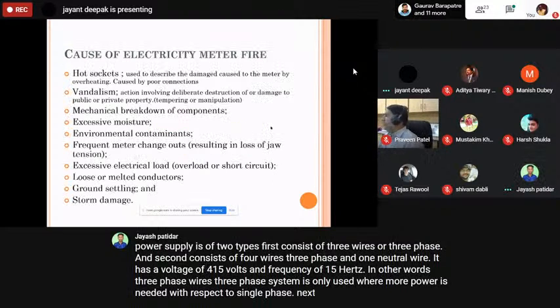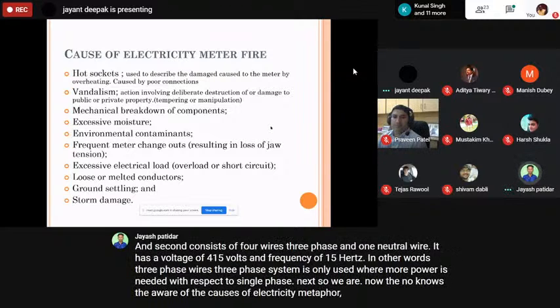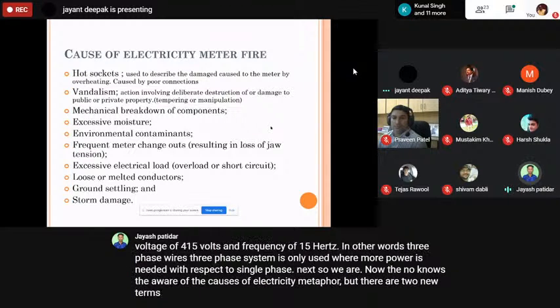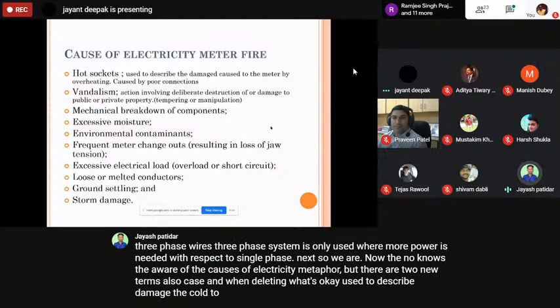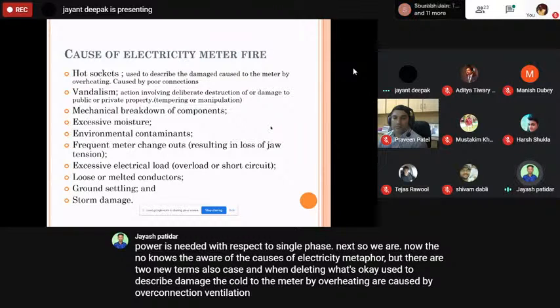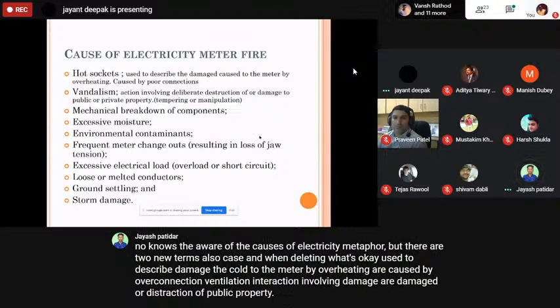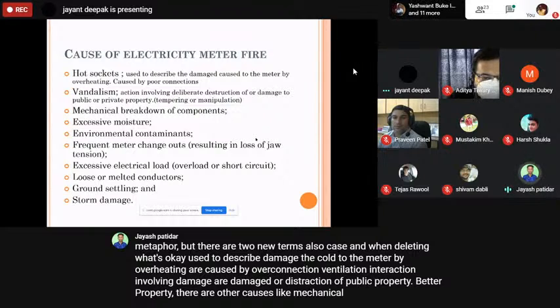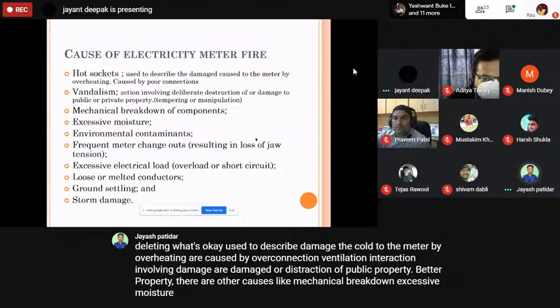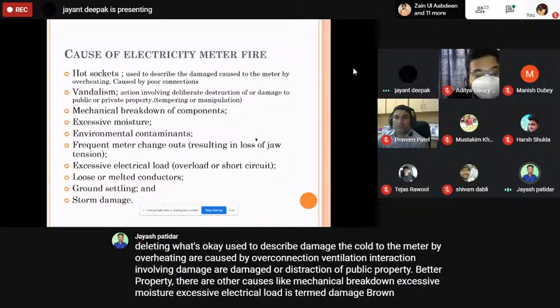Next, we all know the causes of electricity meter fire, but there are two new terms: hot socket and vandalism. Hot socket is used to describe damage caused to the meter by overheating or by poor connection. Vandalism is the action involving damage or destruction of public or private property. There are other causes like mechanical breakdown, excessive moisture, excessive electrical load, storm damage, ground settling, and so on.